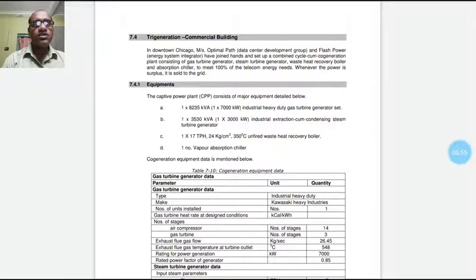So in downtown Chicago, M/s Optimal Path Data Center Development Group and Flash Power Energy System Integrator have joined hands and set up a combined cycle cum cogeneration plant consisting of gas turbine generator, steam turbine generator, waste heat recovery boiler and absorption chiller also, to meet 100% of telecom energy needs. Whenever the power is surplus, they sold it to the grid.